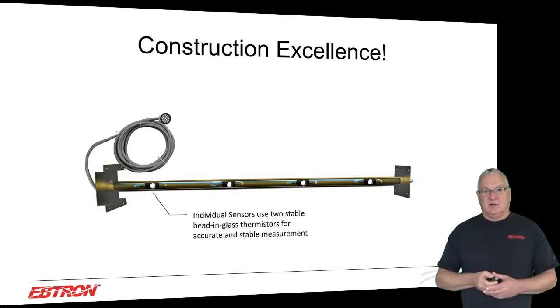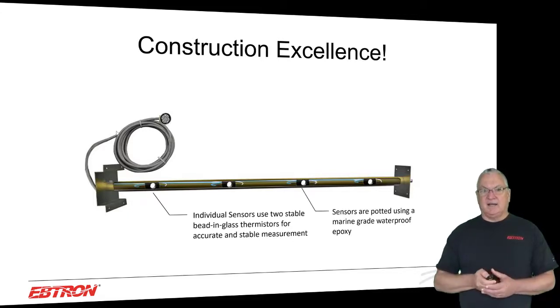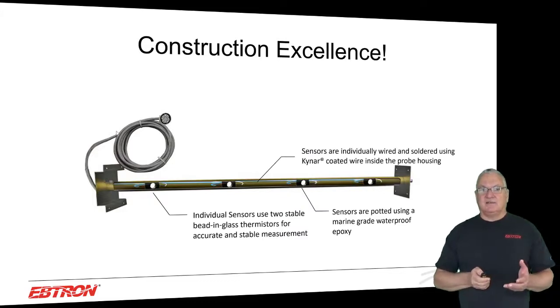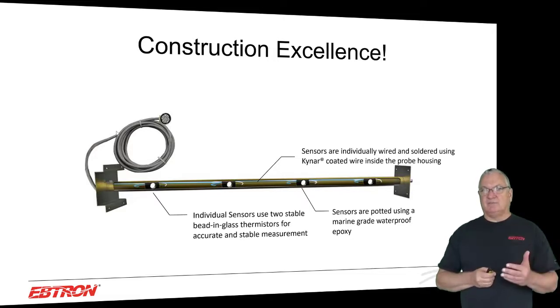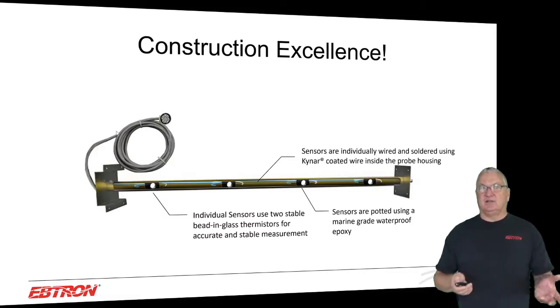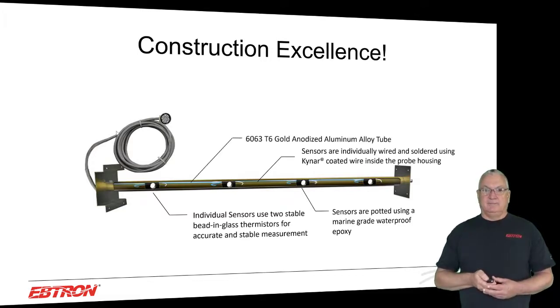All right, so we talked about the beaded glass thermistors, and we talked about the potting. But what we didn't talk about is the fact that all the internal wire is Kynar coated instead of PVC jacketed. And the reason for that is over time, we know that these wires will vibrate, and over time, a PVC jacketed wire will end up wearing through and eventually shorting out to the tube. Okay, so we just use Kynar to start with. We use a very strong aluminum tube, the 6063 T6. They're all gold anodized.